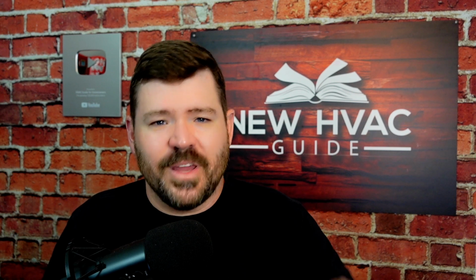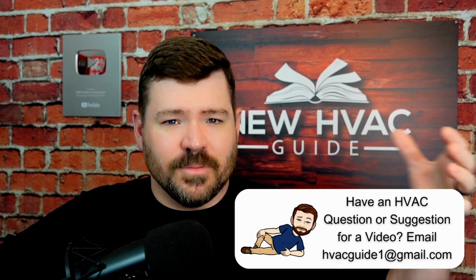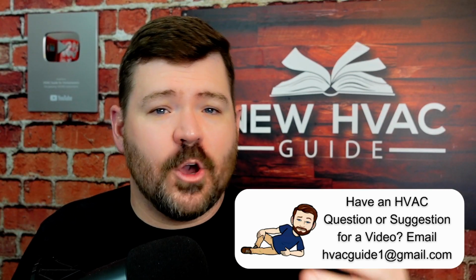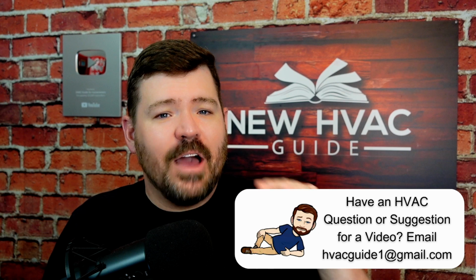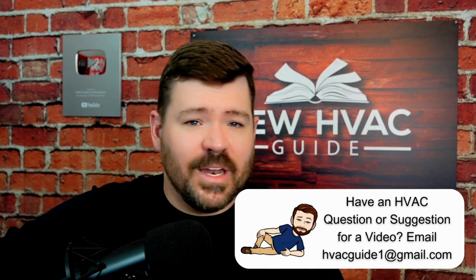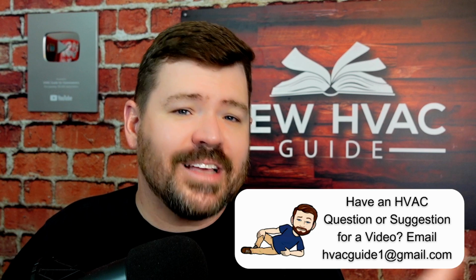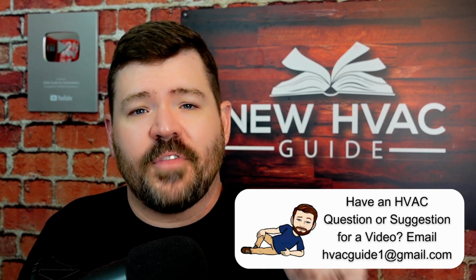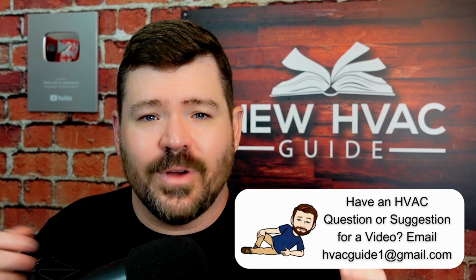Because if not, then that customer is going to experience humidity problems, where they're going to say the humidity levels are higher in here than they used to be with my old clunker. My old system that was 20 years old dehumidified better than this new fancy variable speed inverter system, communicating inverter system. If you found this video because you went with a higher end system and now you're having problems with the humidity, it's louder than it used to be, there are things that can be done to the ductwork. There are things that can be done to the system to try to account for some of this. But ultimately, you're going to be throwing mud on the wall if things are not being done correctly.